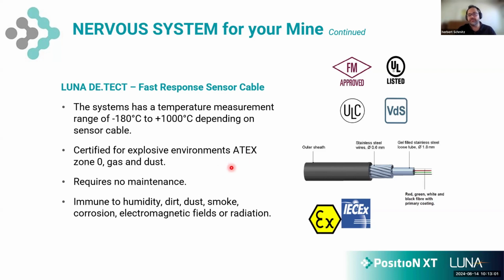One of the major benefits of fiber optics above any other sensing technology is that it requires very little to no maintenance. It's immune to vibration, dirt, dust, smoke, radiation, electromagnetic fields, corrosion. We can run this literally around a transformer, and we do, to monitor their temperatures without affecting our ability to measure. And I always use this argument: if the tunnel would flood, we would know what the water temperature is. So really, really robust sensor that runs throughout the mine.